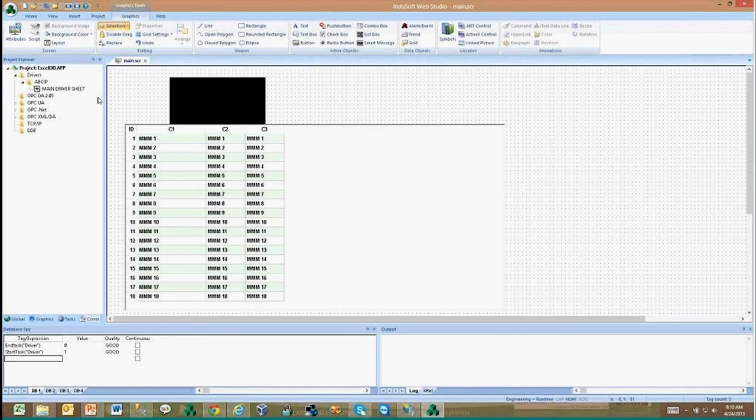So if I try to communicate a tag that has a very long name with many characters, when I transfer the name of this tag, it takes a lot of bytes. In other words, if I try to communicate tags with long names, each communication block will have fewer tags than if I use tag names with really short names, because I do not spend a lot of bytes to send short names to the PLC.